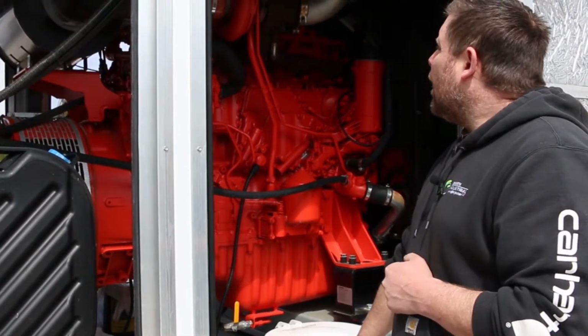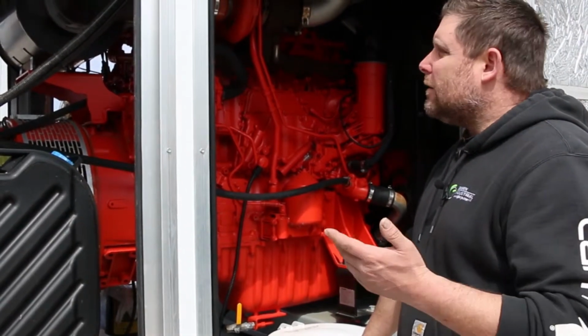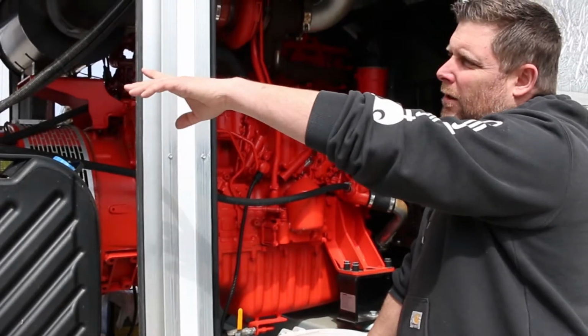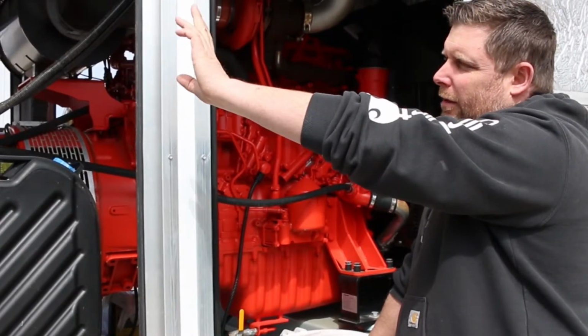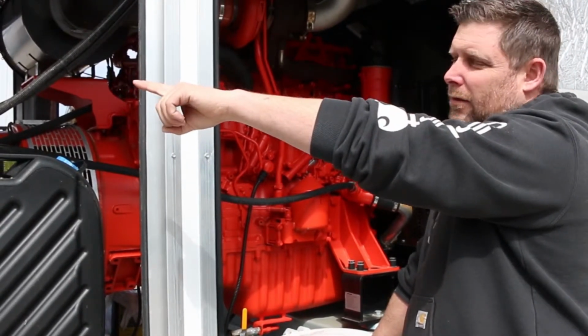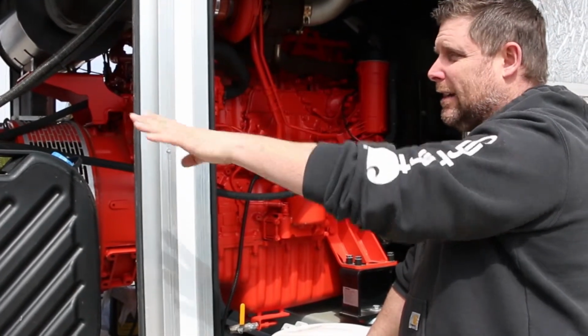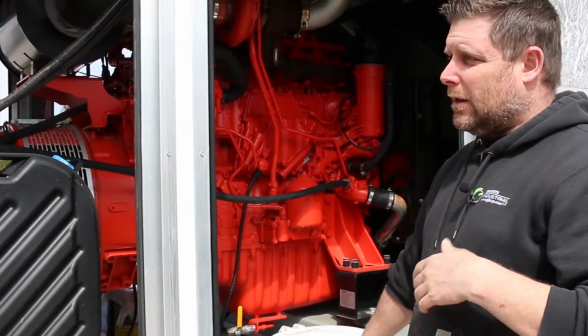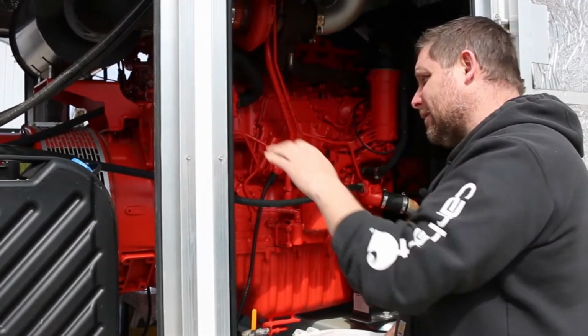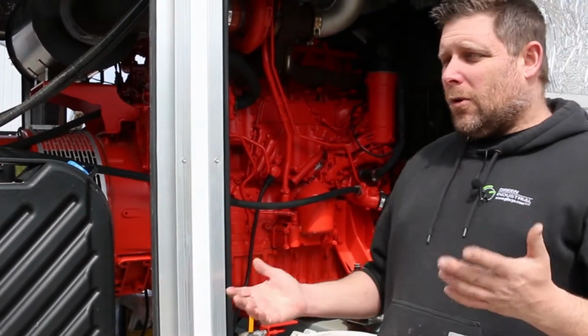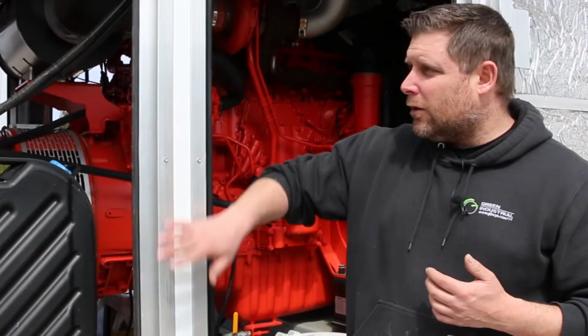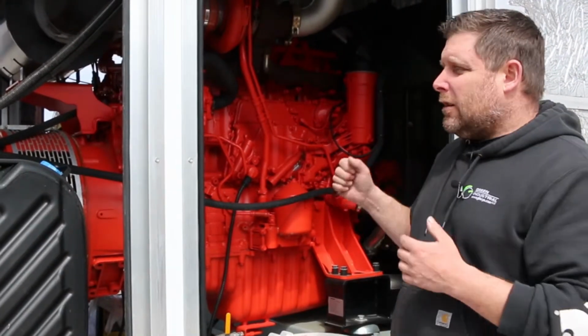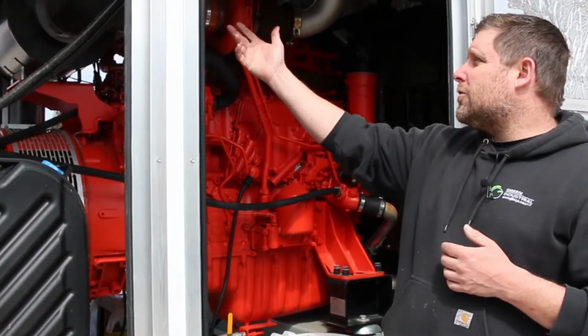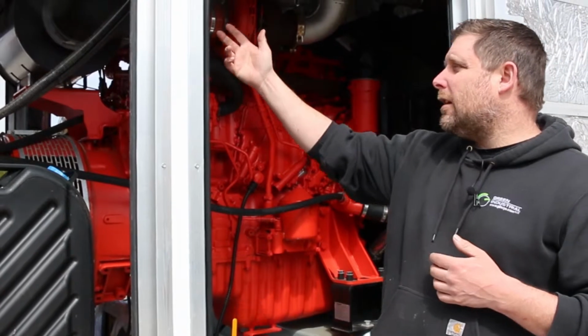So again, with the sound attenuation, there is a transfer switch built right into the switchgear. That's a 1200 amp transfer switch and a NEMA 1 enclosure built right inside this enclosure. So everything's in one package. So you've got your base tank, your enclosure, your transfer switch, your gen set, DEF tank, enclosure, enclosed muffler and everything here, all under one house. That saves you space. It saves you cabling.